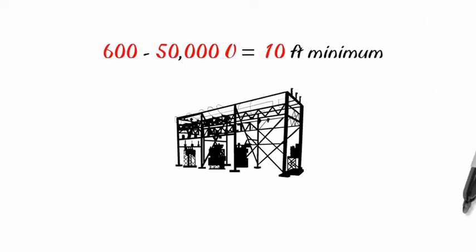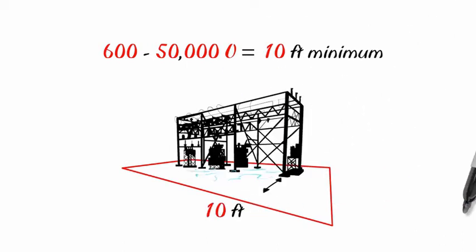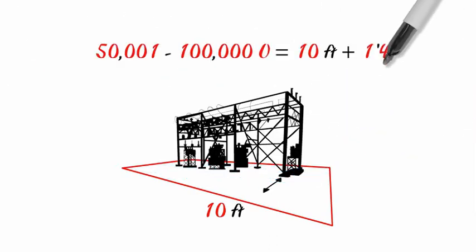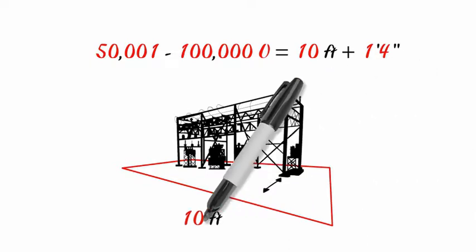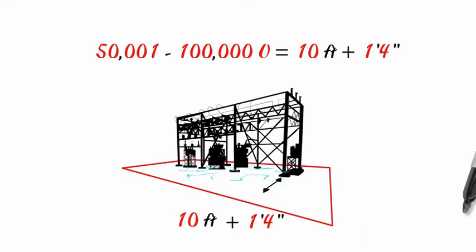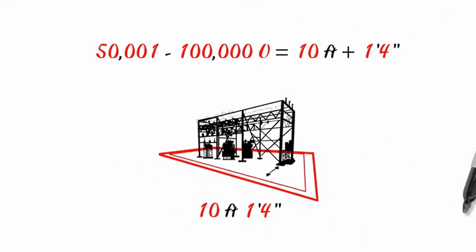With high voltage, it's 600 to 50,000 volts, we stay back 10 feet minimum. If electricity is 50,000 and 1 volt to 100,000 volts, we add 1 foot 4 inches. And it continues to go up as we go.